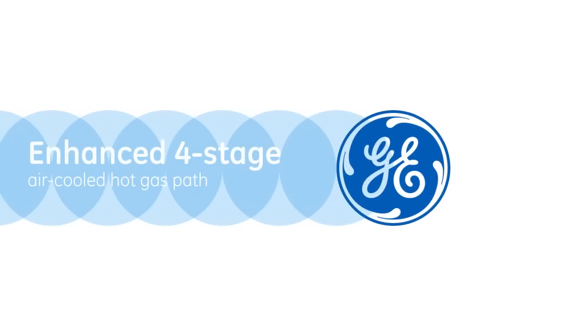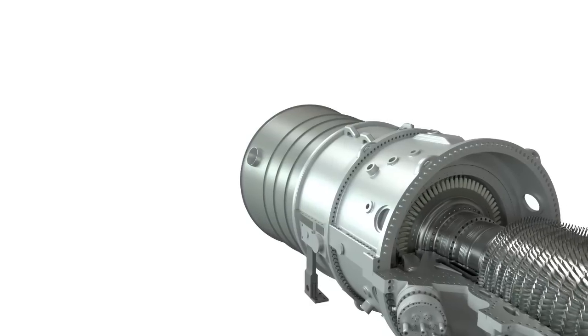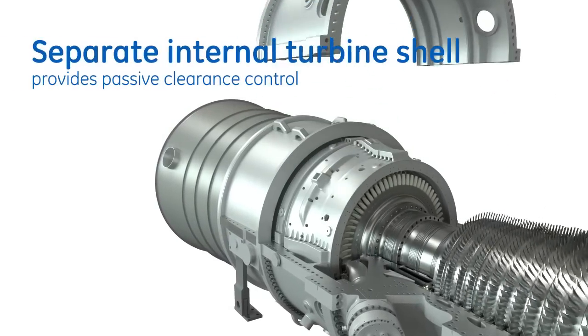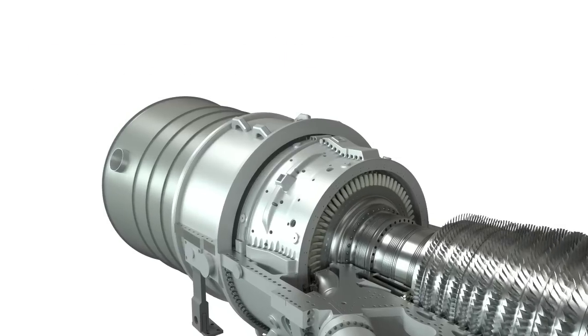The 9HA's four-stage air-cooled hot gas path consists of inner and outer shells to better manage clearances. The inner turbine shell supports close bucket and seal clearances, acting as passive clearance control.